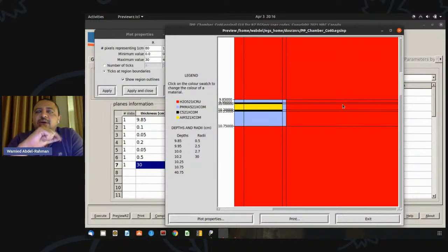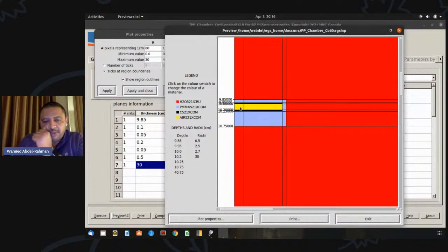The dose or the charge in the chamber, this is basically the dose in this region here. I'm going to assume that this is a perfect chamber. The guard electrodes are really well defined in the conduction volume of the ions. So the charge within the air in this region here, that is the Q. That's the dosimetric signal. But in Monte Carlo, we get a dose. We don't get a charge. So how do we convert this to charge?